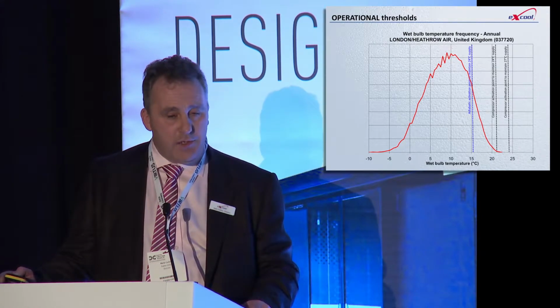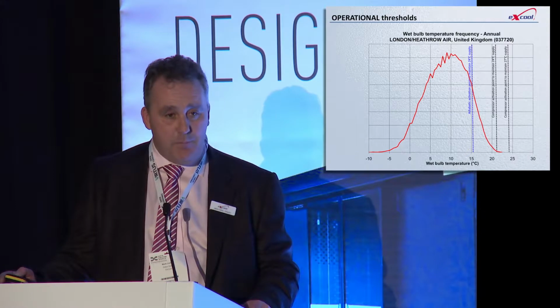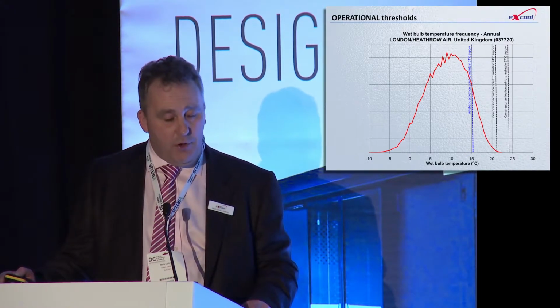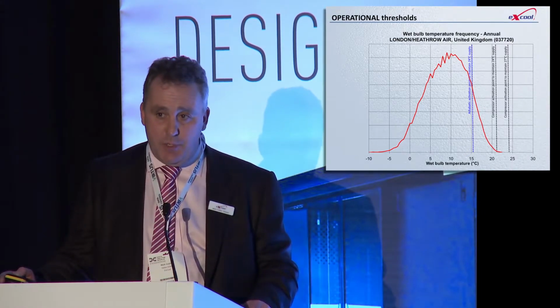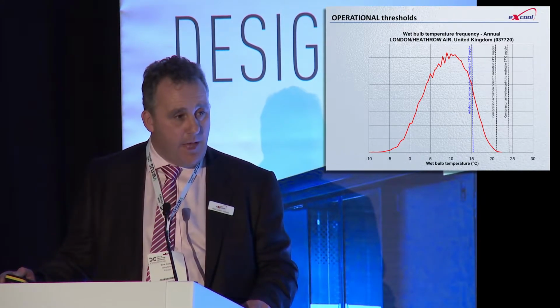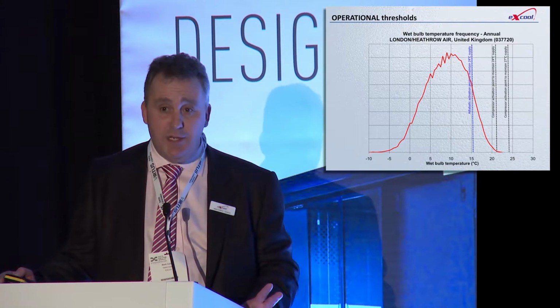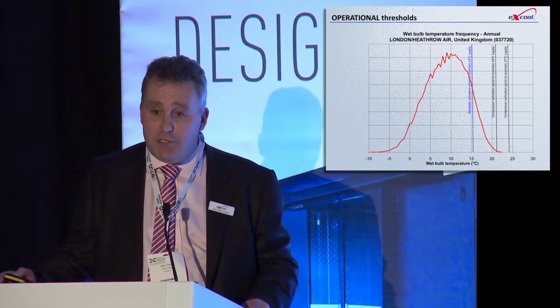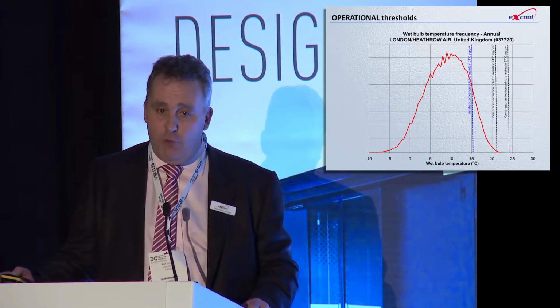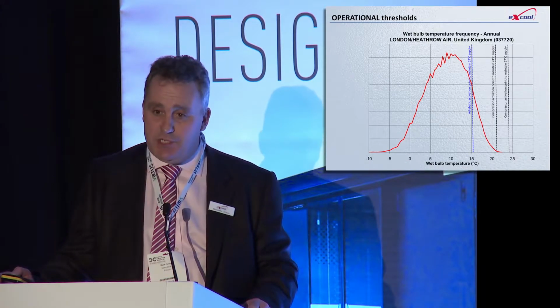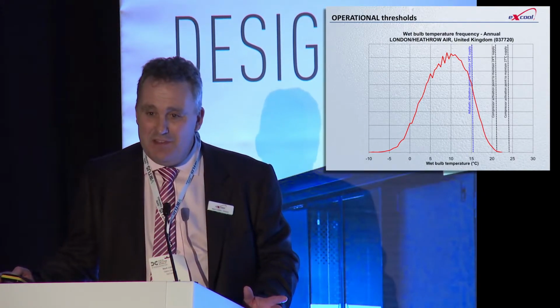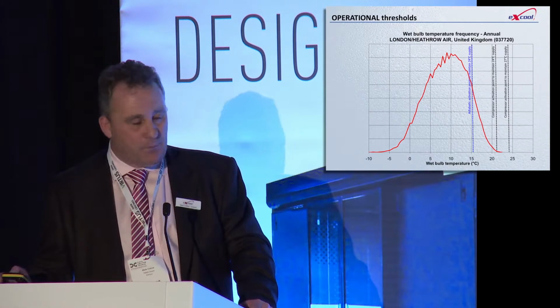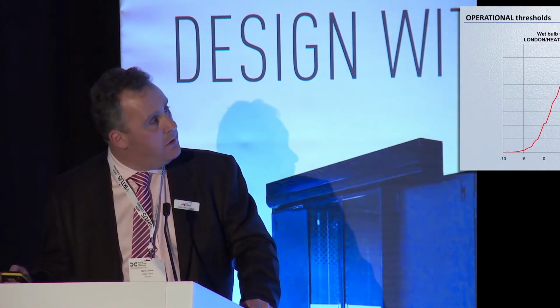What most of our clients are saying is that I'm not going to put compressors in there, even if it may only be 25% of the total load. I'm still not going to use compressors for those 2 hours per year. I'm just going to allow the temperature to rise above 24 degrees C, maybe up to 26 degrees C for maybe 2 hours a year. And by doing that, I avoid the need for compressors. So he needs to rewrite the standard service level agreement to accommodate that.